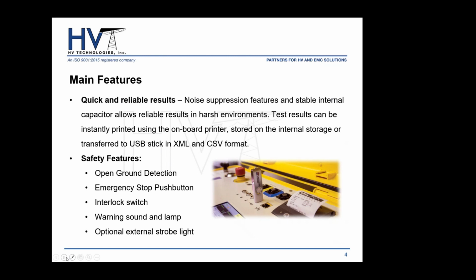A little bit in with instruments that use high voltage, of course, safety is paramount. So the MIDAS Micro also boasts some pretty good safety features, like open ground detection, which basically, if the safety ground of the instrument is not connected, the instrument will not generate high voltage. We also have an emergency stop push button locally on the front panel of the instrument, which will effectively cut the high power generation instantly.